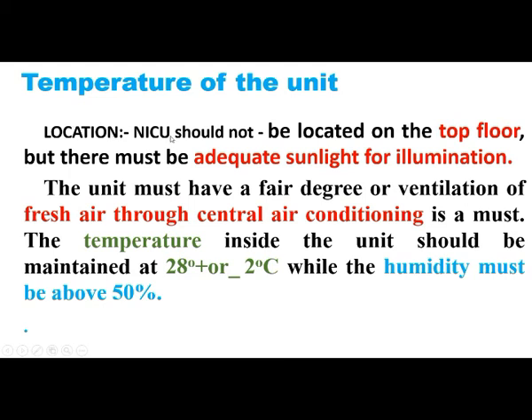The NICU should not be located on the top floor, but there must be adequate sunlight for illumination. The unit must have a fair degree of ventilation of fresh air; central air conditioning is a must. The temperature inside the unit should be maintained at 28 degrees plus or minus 2 degrees Celsius, while the humidity must be above 50%.